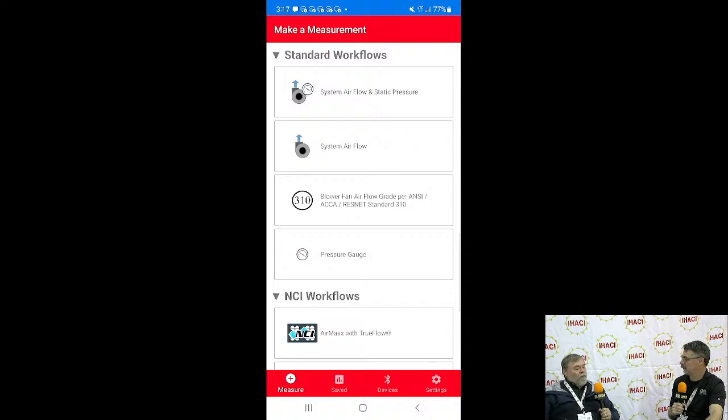Yeah. But with all that testing, you have a baseline to look at the system. You have a benchmark that you can use to say this is where you're at now. Let's go do the load calc. Let's see how it all compares and see where you're at. Because it's amazing. And then I go a step further. I usually do the ASHRAE 221, and I take my readings on the equipment and find the efficiency of the equipment, and we show all the different problems that the system has.